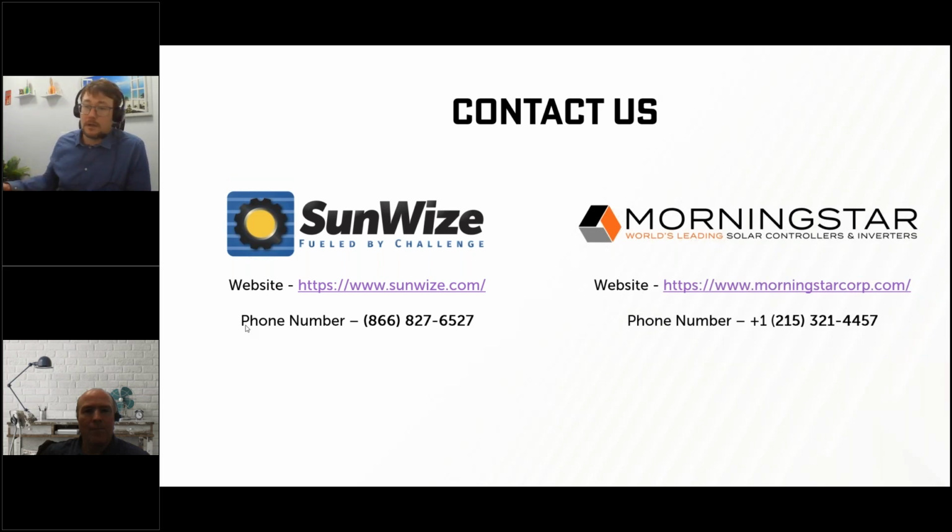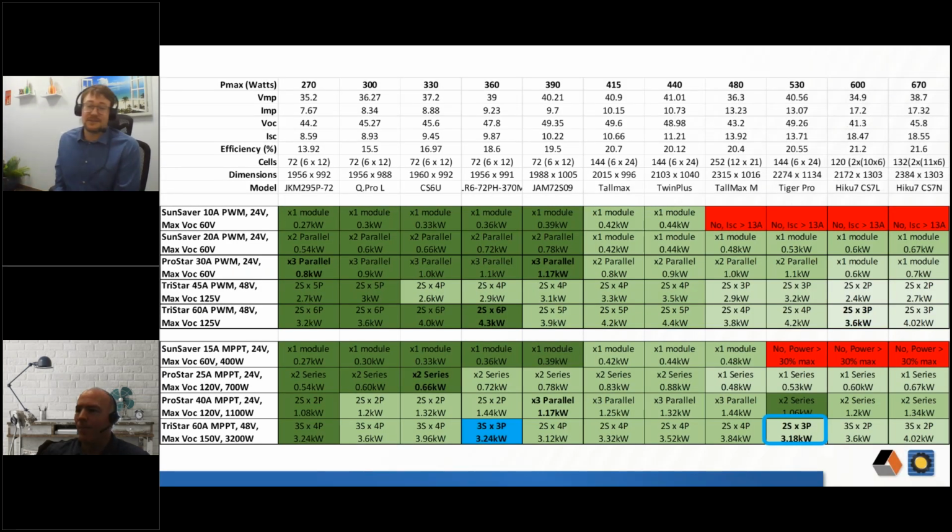So here's the deal with bifacial, and I'll go to the next slide, just so I can speak about some of the rest of this. Just like I said, this whole table is dependent on the background variable about what manufacturer you're talking about and what rules apply. Of course, this whole table gets massively shifted when you're talking about a bifacial version of these modules. Every single module I have listed here is a monofacial. So these 670 watt modules are not bifacial, but they also have bifacial versions of them. I believe I have it right in my Excel file to the right of this. In this particular case, the bifacial equivalent of this exact 670 watt module has an ISC of 22.5 versus 18.5.